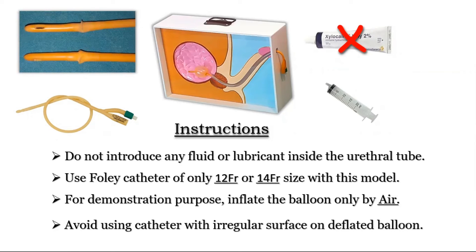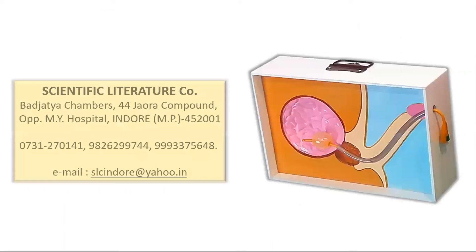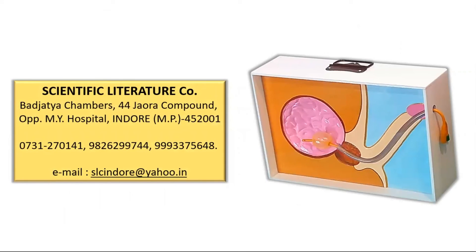After repeated use, the catheter may develop some wrinkling on its balloon, and it may be difficult to pass such a catheter through the curvature of the tube — in such a case, please start using a new catheter. At present, that is in October 2022, this model is available at only one agency, which is Scientific Literature Company in Indore. You can communicate with the dealer through mail or phone call.